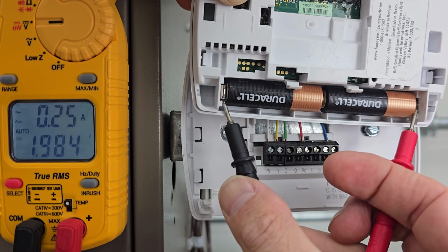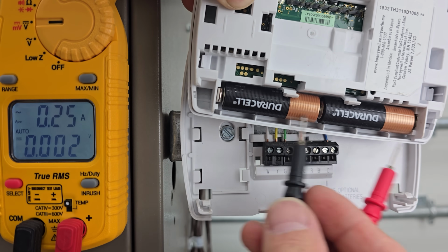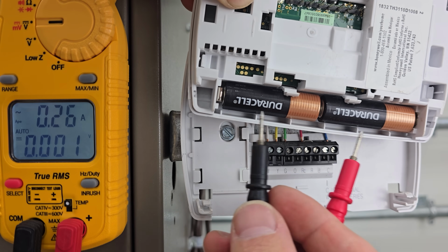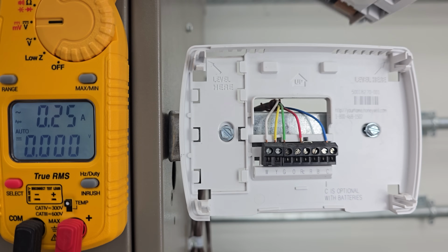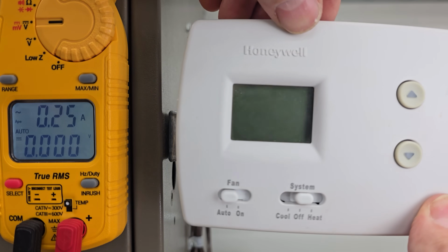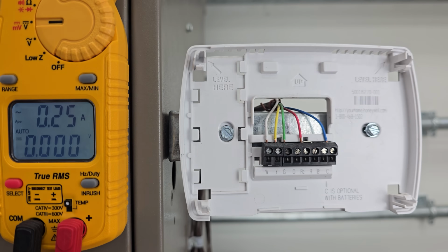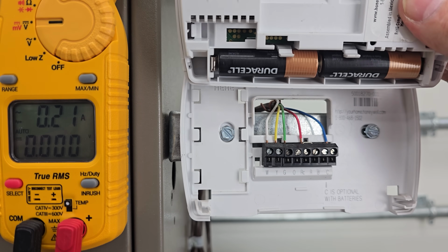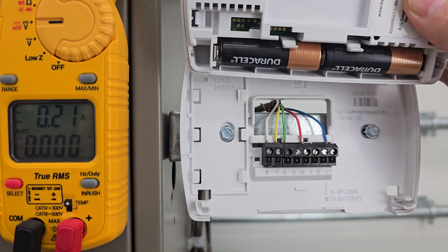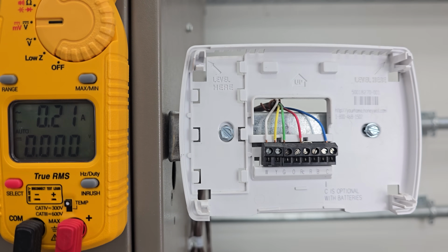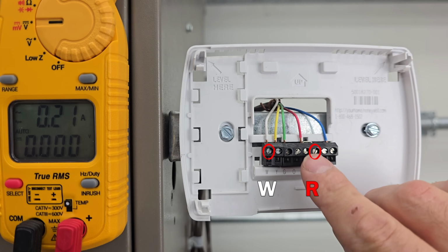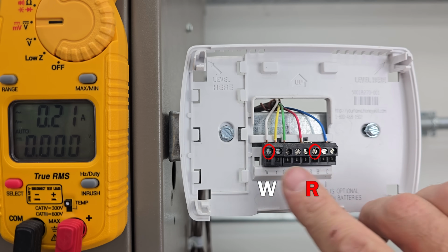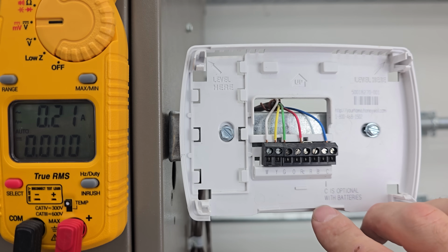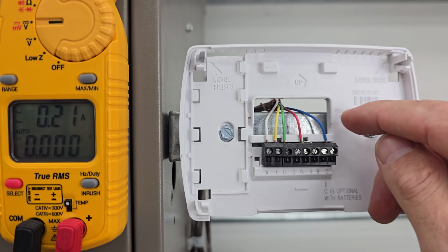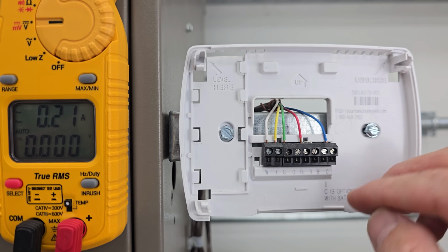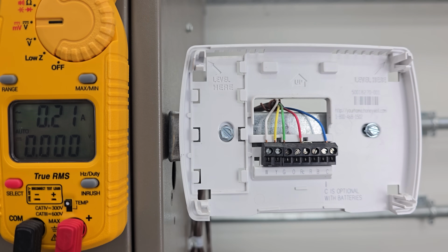So as these batteries are used up, the voltage lessens until basically it does not have enough power to turn the thermostat on. That's going to be our issue. Now, even if we did have good batteries here, the thermostat would turn on, but you did notice earlier I jumped between R and W and nothing happened inside the furnace. And so there must be some other issue besides maybe a problem with our common wire. And so we need to diagnose down in the blower compartment.